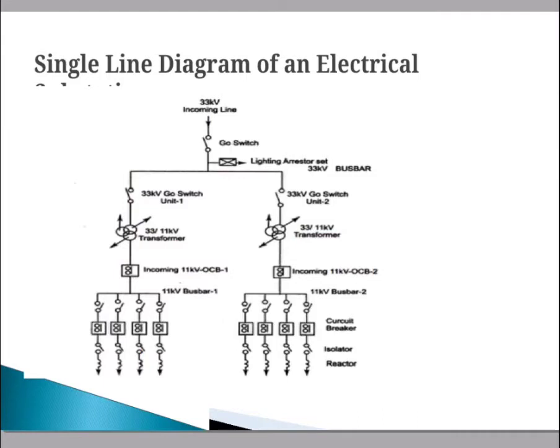On the incoming 33 kV feeder line side, the transformer is connected to the bus bar, and the lightning or surge arrestors are connected phase to ground as the initial connection equipment. A circuit breaker is connected between the 11 kV bus bar and each incoming and outgoing circuit, with an isolator provided on each side of the circuit breaker.